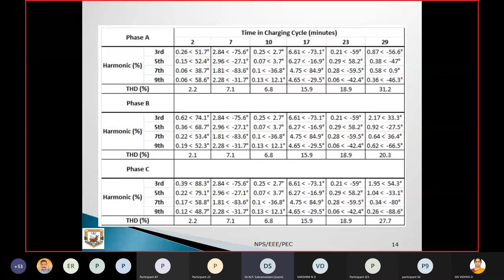Now, total demand distortion factor: the feeder is more charged and in use concurrently. You can see here, the total demand distortion factor is also considerably higher, so it will also violate your system. This should be below 10% as per IEEE 519-1995 standard, but here you can see this is considerably high, so this also needs to be taken care of. Both THD and total demand distortion factor are considerably high. If you allow more chargers during more cycles, it will cause big stress to the system.